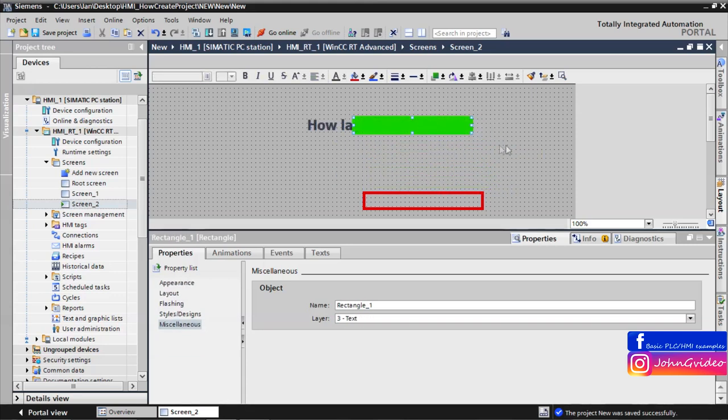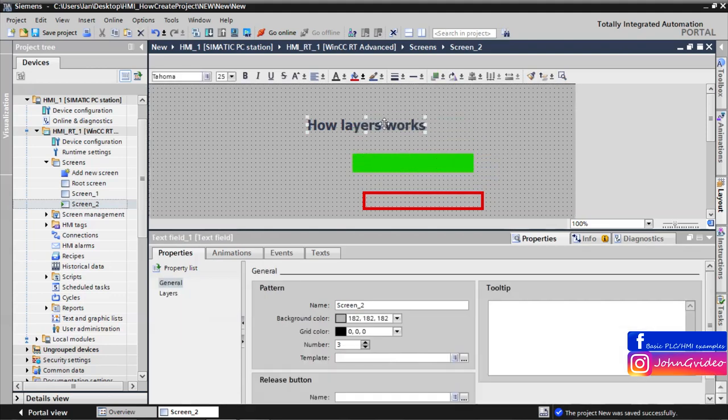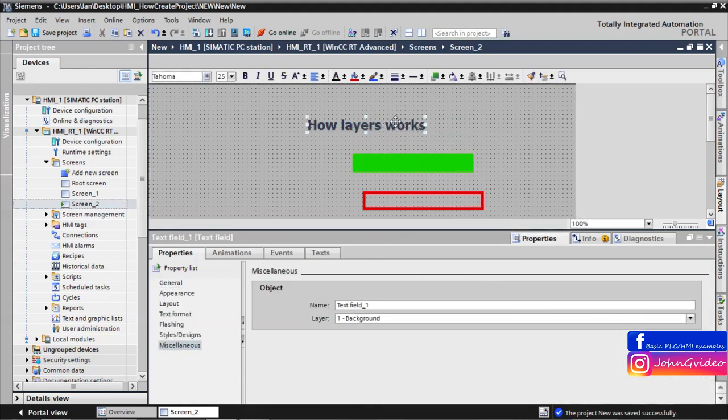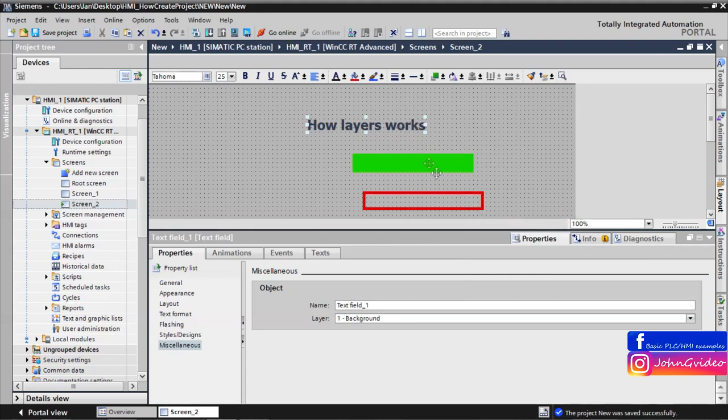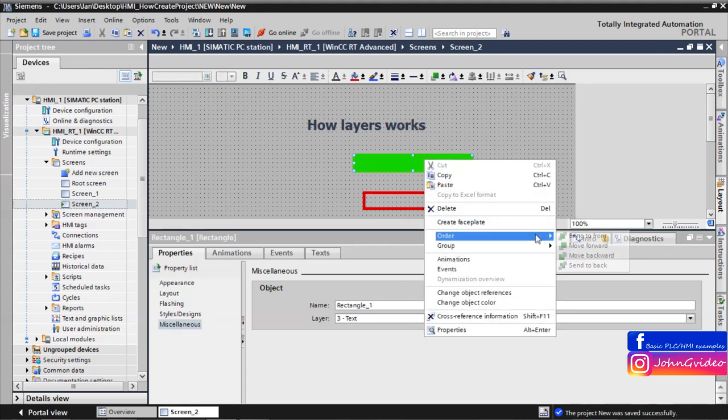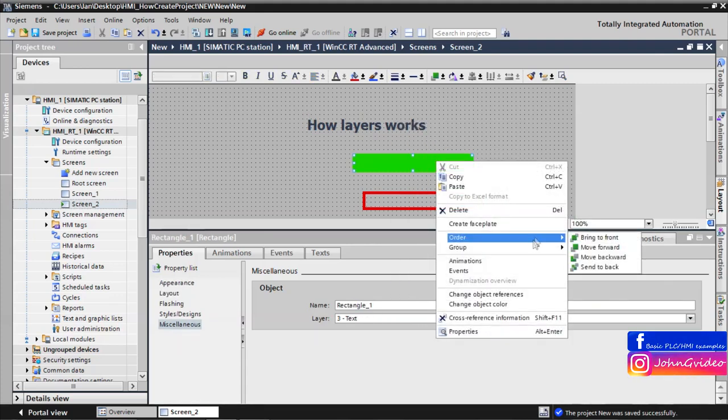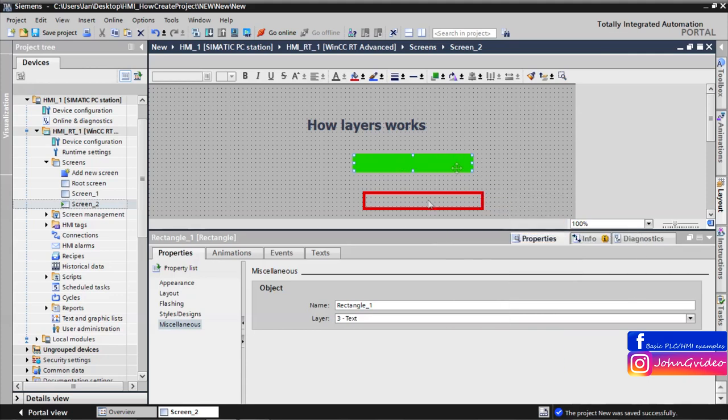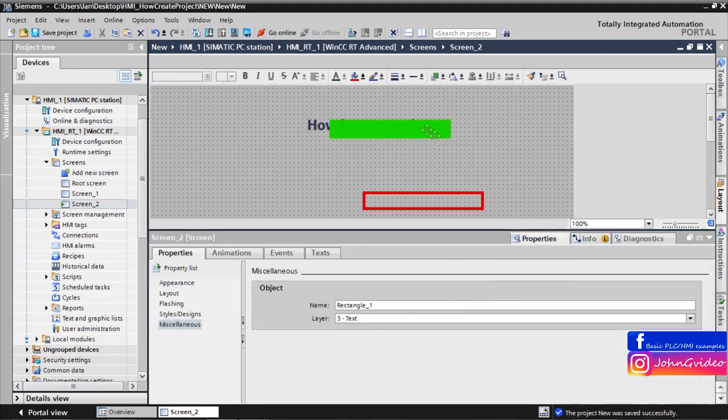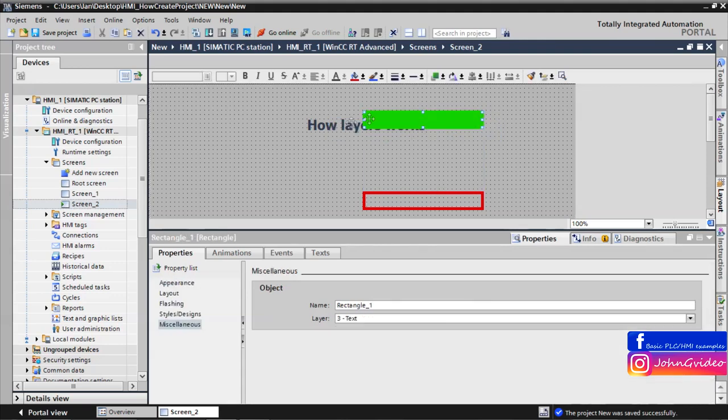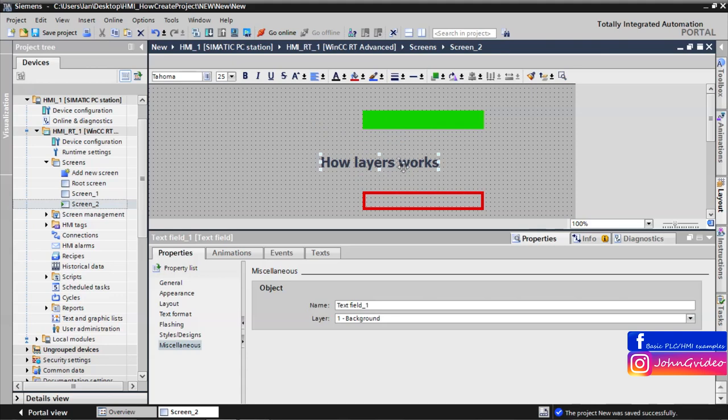And now here you can see how this hierarchy works. You can see, text is still behind the rectangle. Also, if you use bring to front, move to forward for the text, and move backward and send to back for the background, still the rectangle is before the text. This is the hierarchy in the layers in WinCC.